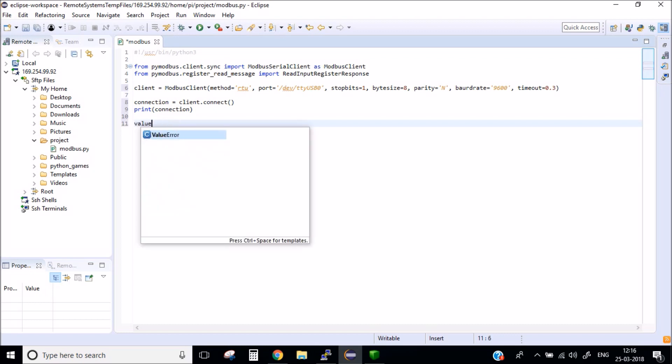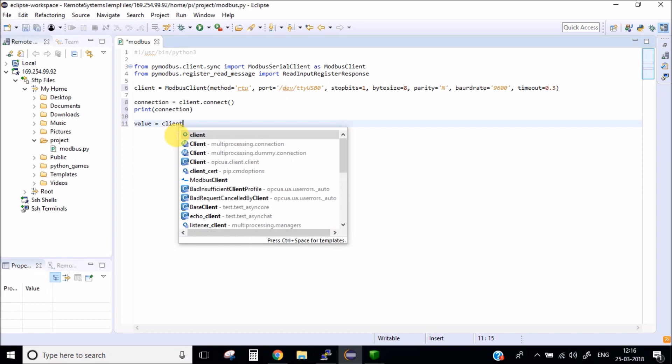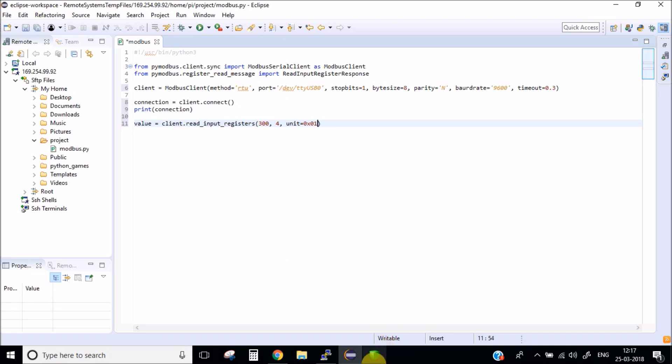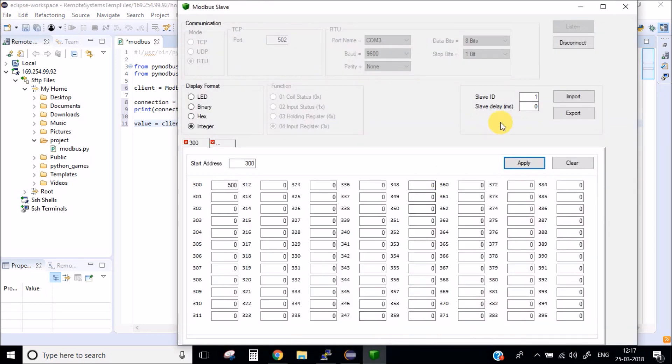Now after this we need to simply read the values, read the value of the input registers. Here we need to mention the register which we are going to use. We are going to use 300 register. Let's say the size is 4. And here we need to mention the slave ID. Slave ID we are using is 1.